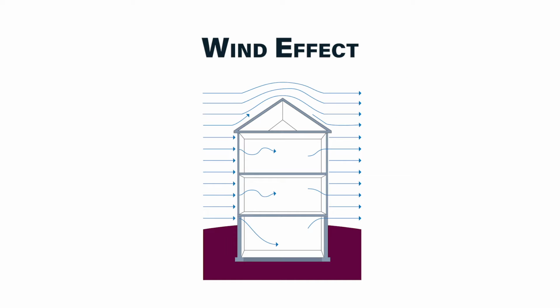The first way is from wind. Wind creates a positive pressure on the windward-facing walls and negative pressure on the non-windward or leeward-facing walls. This difference in pressure causes air to enter or leave the building through openings in the envelope.